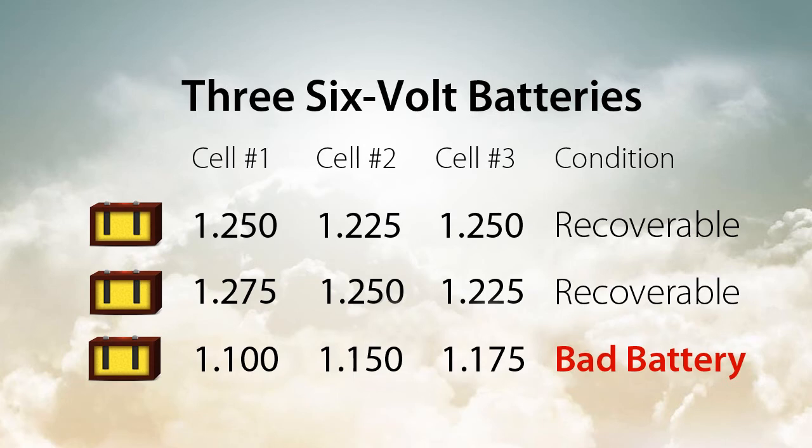In this example, battery C has an open cell because the difference between cell number 1 and cell number 3 is 0.075, more than 0.05.